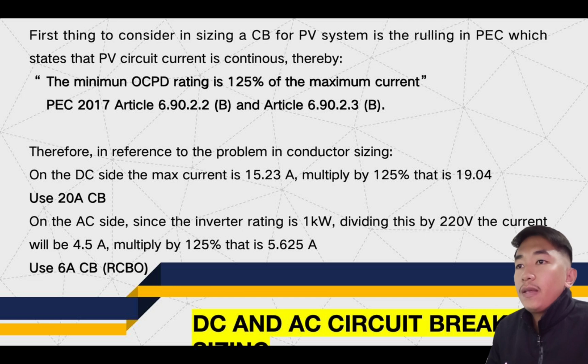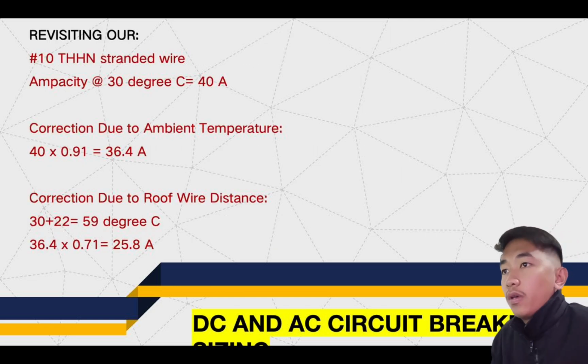since the inverter rating is 1 kilowatt, dividing this by 220 volts, so the formula for current is power divided by voltage. So dividing this by 220 volts, the current will be 4.5 ampere. Multiply by 125%, that is 5.625 ampere. So wala din exact na 5.625 ampere. So we use 6 ampere circuit breakers. So that's RCBO. Revisiting our number 10 THHN stranded wire. Ampacity at 30 degrees Celsius is equals to 40 ampere.